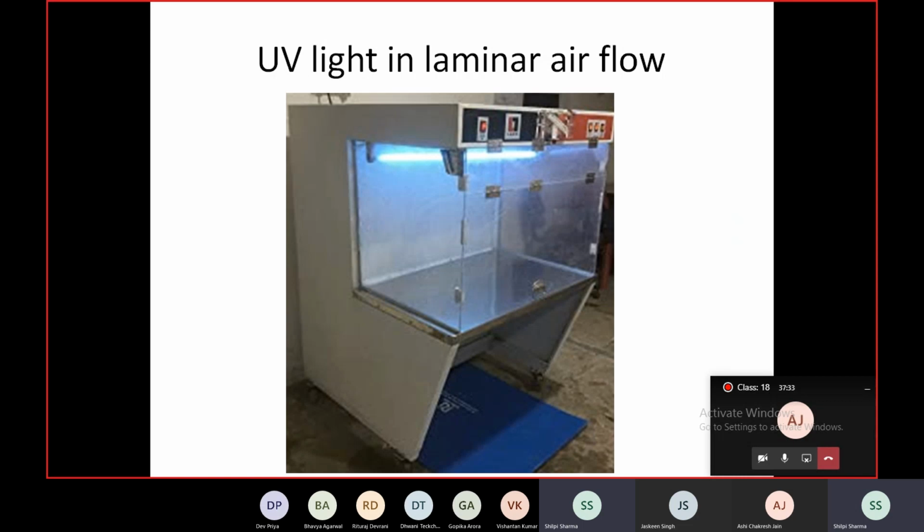just like a biosafety cabinet. The laminar flow is also fitted with UV lights, which are switched on before a user starts working so as to sterilize the surface of the workbench and other small equipment that might also be placed in the chamber. In fact, we place our spreaders and the inoculating loop as well, and then turn on the UV. When one starts working, a burner is lit inside for routinely decontaminating the inoculating loop or even heating up a flask before pouring the liquid medium or molten agar. So you will perform all these experiments, and in the UG lab, you will see that we have 3 of these laminar flows kept side by side. So you'll be working under these conditions.